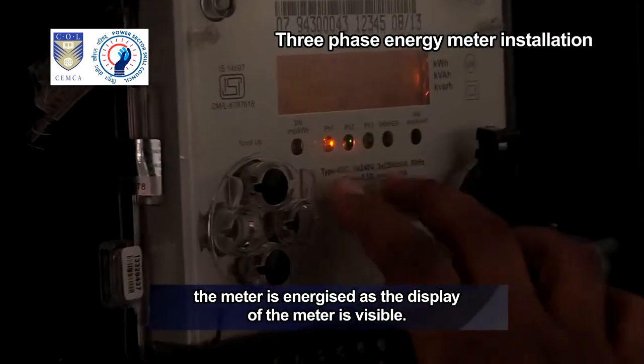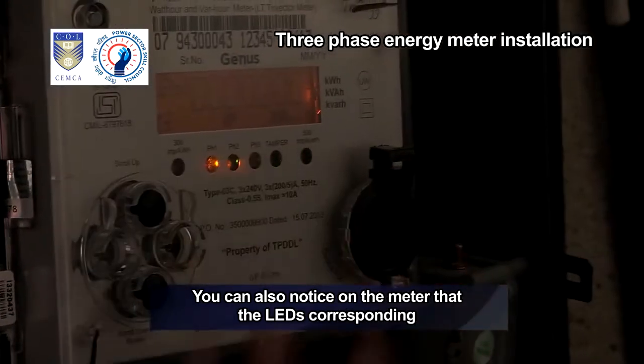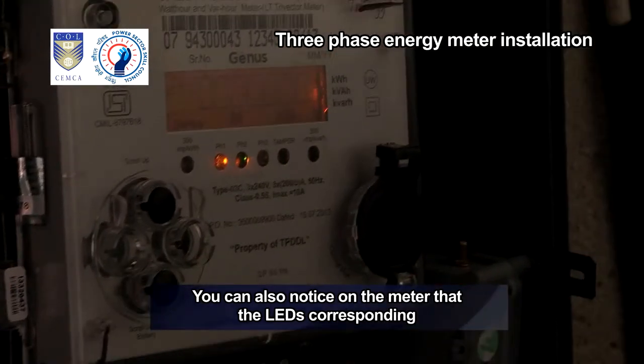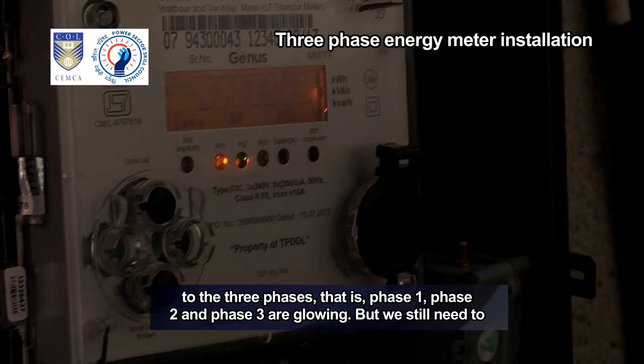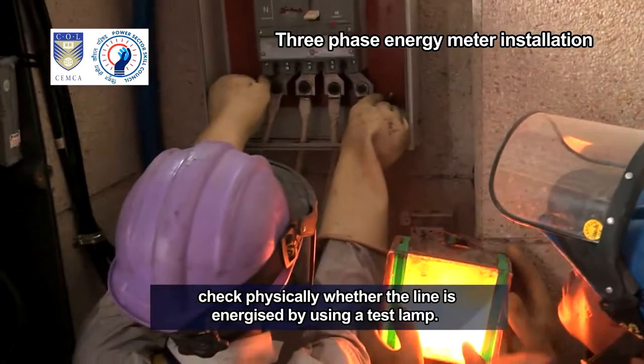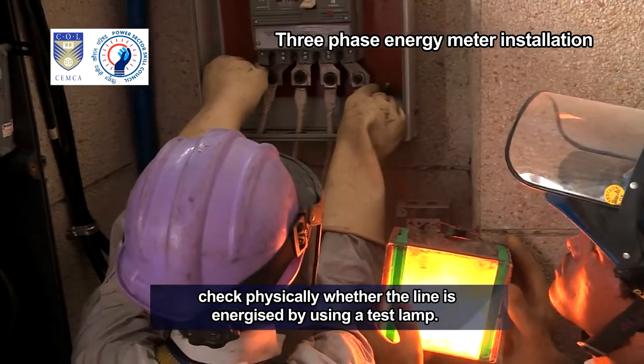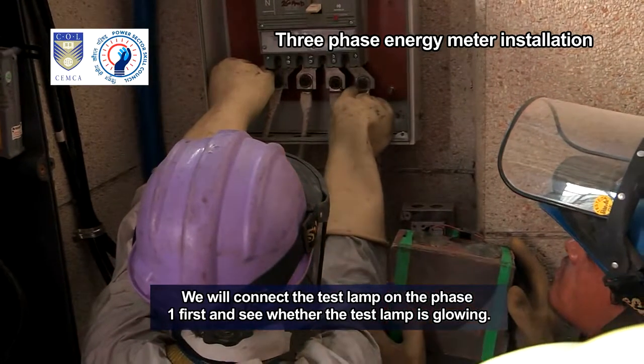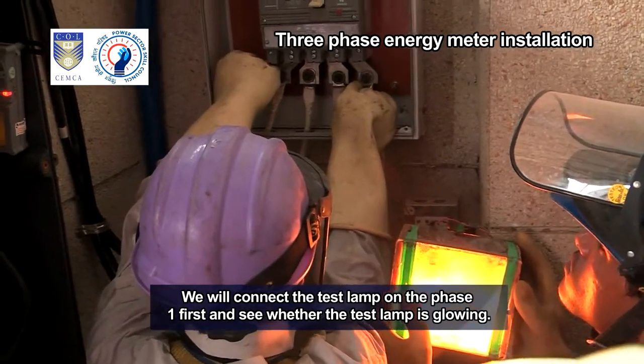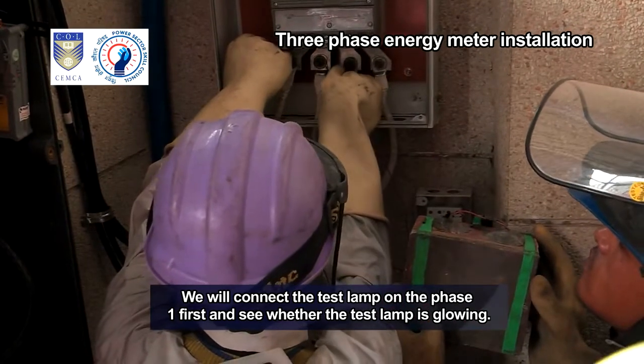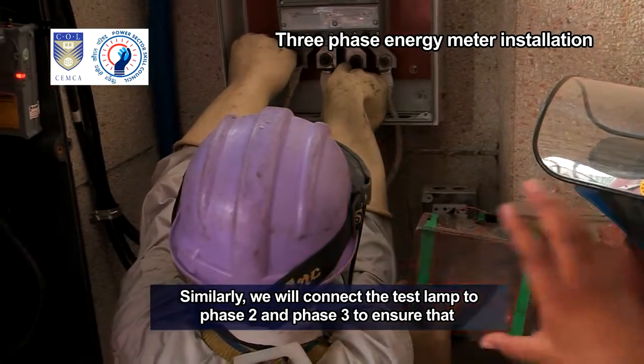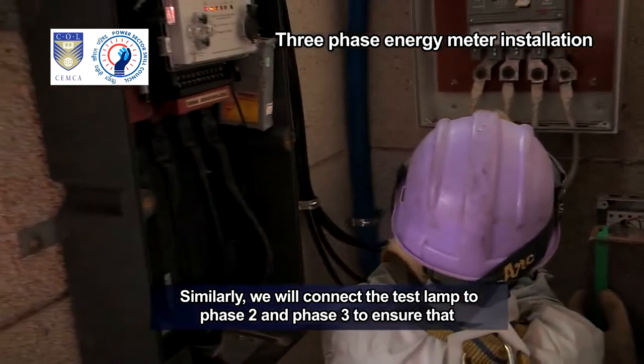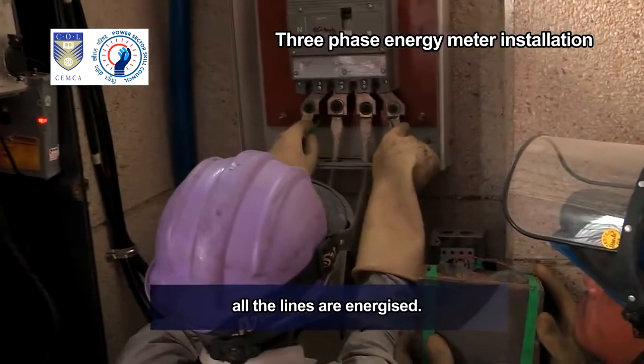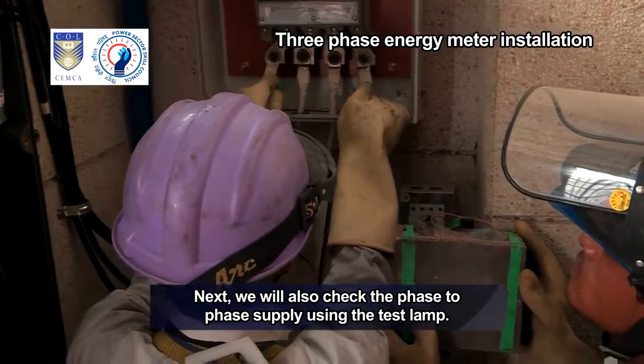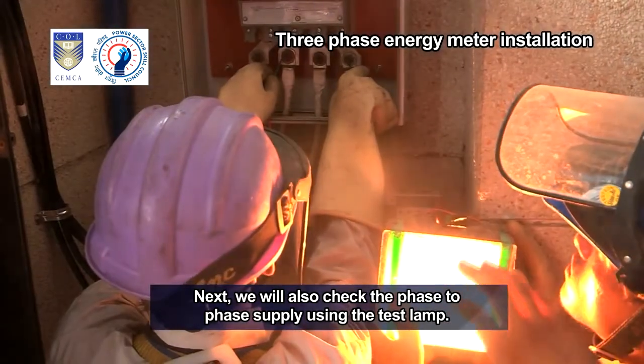As the display of the meter is visible, you can also notice on the meter that the LEDs corresponding to the 3 phases, that is, phase 1, phase 2 and phase 3 are glowing. But we still need to check physically whether the line is energized by using a test lamp. We will connect the test lamp on the phase 1 first and see whether the test lamp is glowing. Similarly, we will connect the test lamp to phase 2 and phase 3 to ensure that all the lines are energized. Next, we will also check the phase to phase supply using the test lamp.